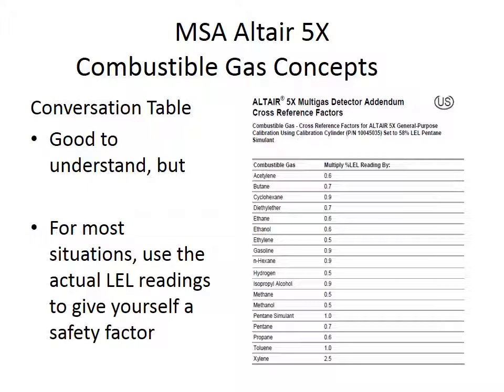Another reason we want you to not worry about applying this table in these situations is that when you're at the entry point, you might be at 10% LEL, but where is the level, say, up on the second floor? Natural gas rises, so perhaps you're at 10% at the entryway, but maybe you're at 80% LEL or at LEL on the second floor. So just give yourself a safety factor. Where this would really come into play, if you look at that table, you see xylene at the bottom. The factor is 2.5, you would multiply that by your LEL reading, and that would obviously increase from what the meter is telling you. But really, the situations where we'd be sampling for an environment like that would be pretty much none. We really don't have xylene plants or much use of that kind of chemical or combustible gas in this area. But still, it's good to have an understanding of how the meter works.